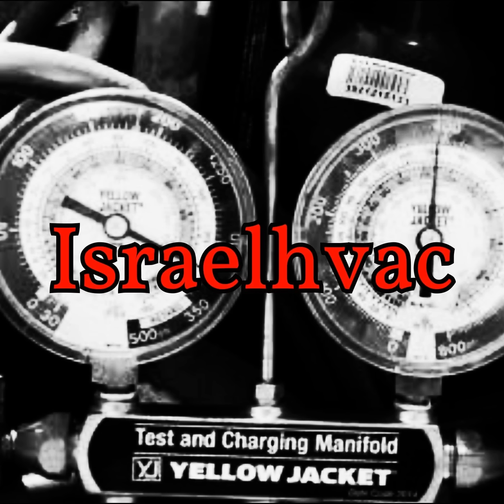So anyway, I heard him say that, and I'm thinking in my head, yep, you sure should have. But anyway, I popped the dual run on there, and before I put the disconnect in, I said, okay, man, you might have got lucky here, but remember, you need to change this thing out. He's like, yeah, I know. So I popped the disconnect in there, and then, just like I said, I heard the noise. I popped the gauges on there, running 150 over 150, equal pressures, running but not pumping.